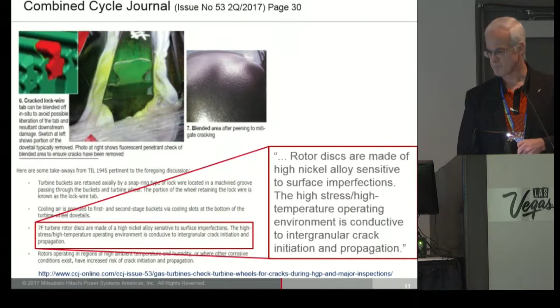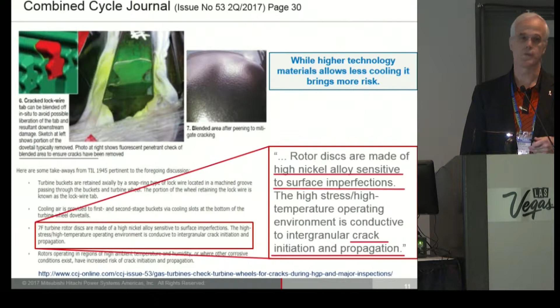Also, this graphic shows some more from the same article. Rotor discs are made of high nickel alloys, which are sensitive to high temperatures and surface imperfections. Crack initiation and propagation is a definite issue with them. So again, Mitsubishi's equipment all has coolers for the cooling air in order to keep the temperatures down, so we don't need to use these materials that have this additional failure mode.